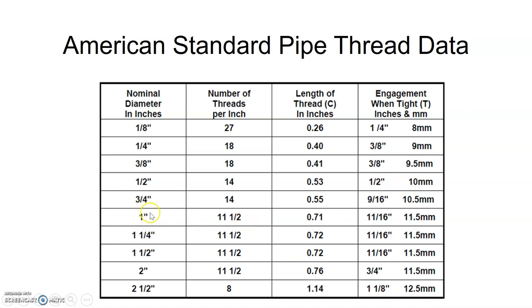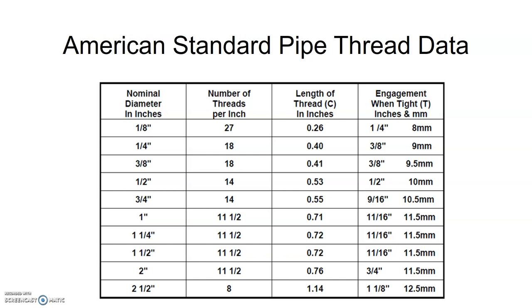Again, if you had a one-inch pipe, the one-inch pipe will have a thread engagement of 11 sixteenths of an inch. So this is how we have to read it. We have to get our face to center measurement by either measuring it or getting it off a manufacturer's table who made the fittings. Once we determine that, then we need to get our thread engagement, and for our thread engagement we need to know our nominal pipe size so we can go to our American Standard Pipe Thread Data table to get that measurement.